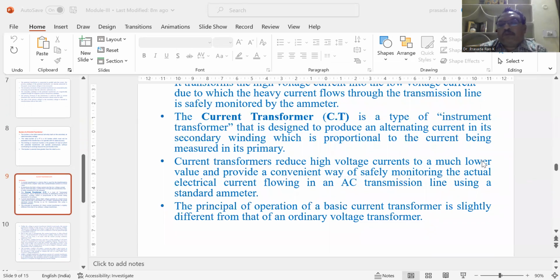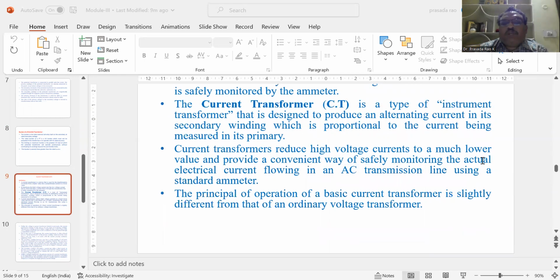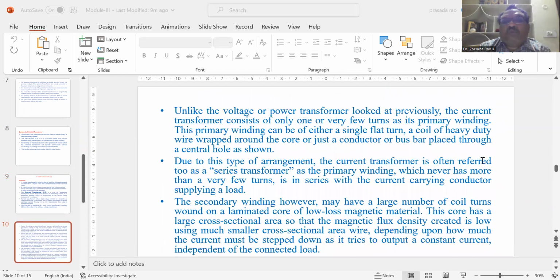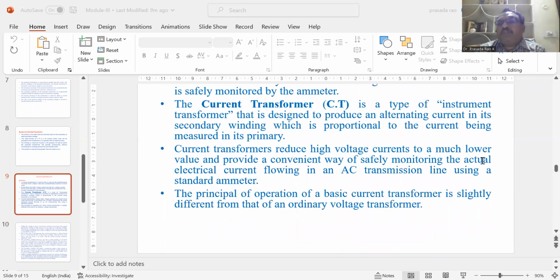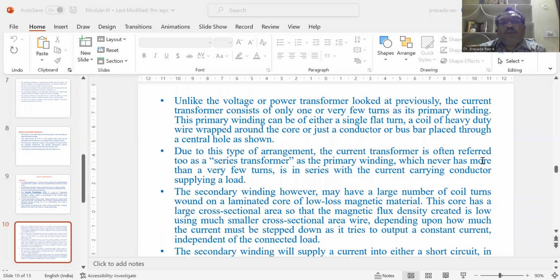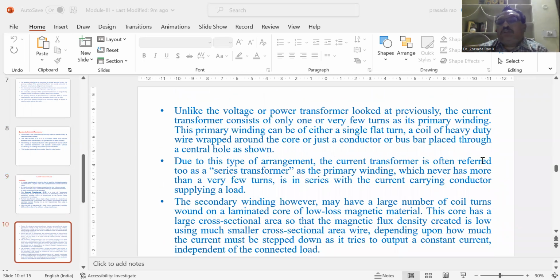The principle of operation of a current transformer is slightly different from an ordinary voltage transformer. Unlike the voltage transformer looked at previously, this current transformer consists of only one or very few turns as its primary winding. This primary winding can be either a single flat turn, a coil of heavy duty wire wrapped around the core, or just a conductor or bus bar placed through a central hole as shown.